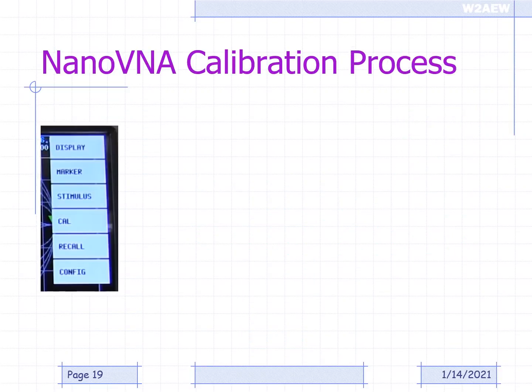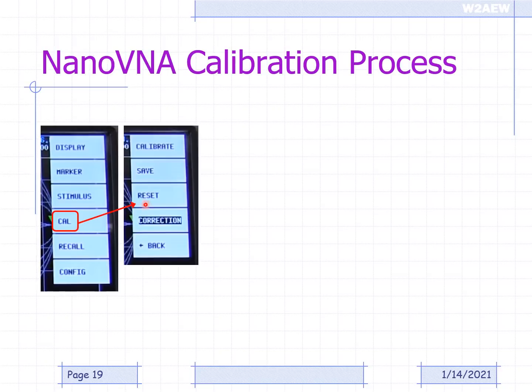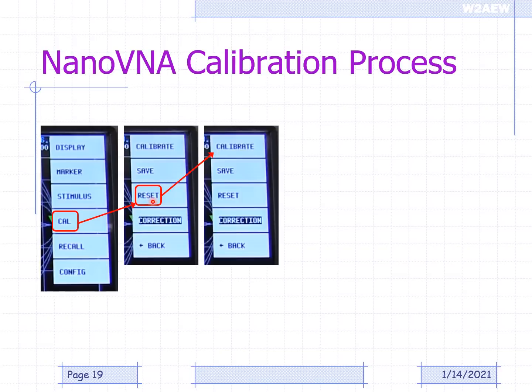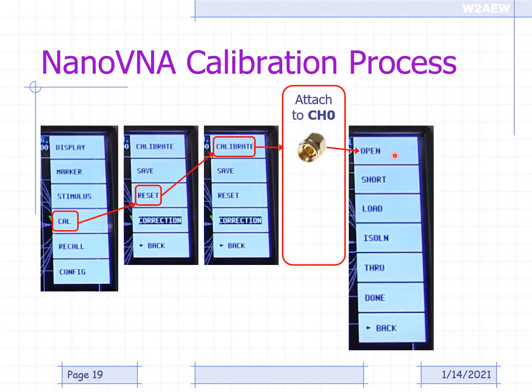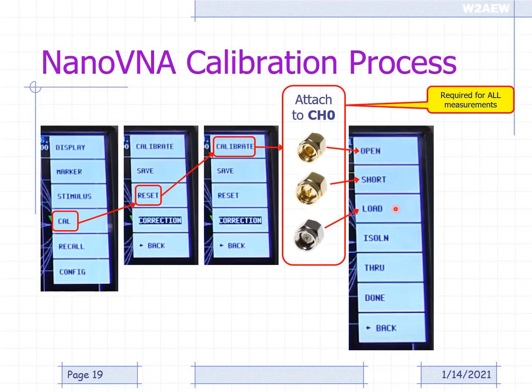And this is the process. It's actually pretty simple. Go from the main menu, you hit Cal, and then Reset. Once you hit Reset to clear the current calibration, you hit Calibrate, and that will bring up this menu on the side here, prompting you to attach the open to channel 0. You do that, touch open, and then you do the same thing for short and for load. And again, this is required for doing all measurements.